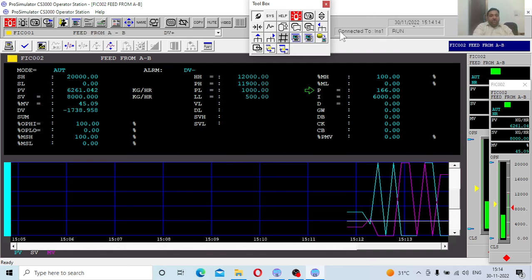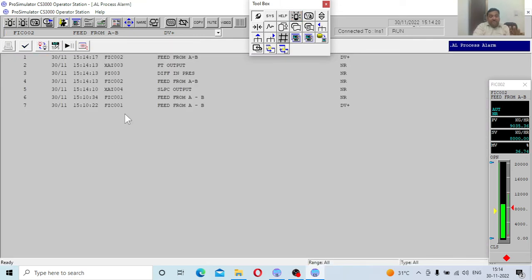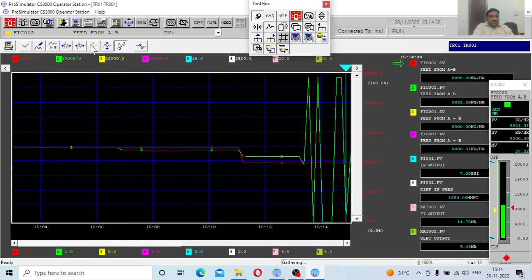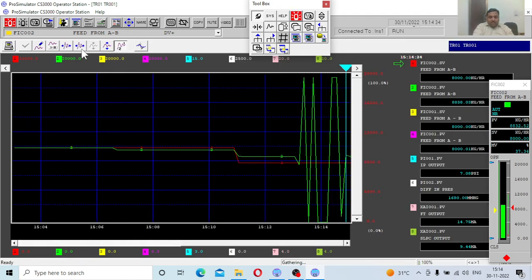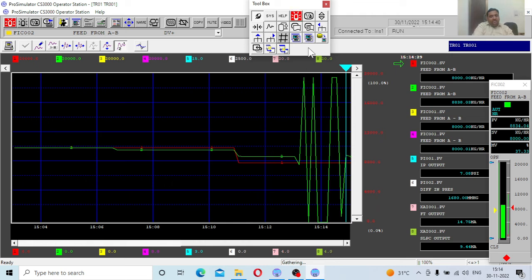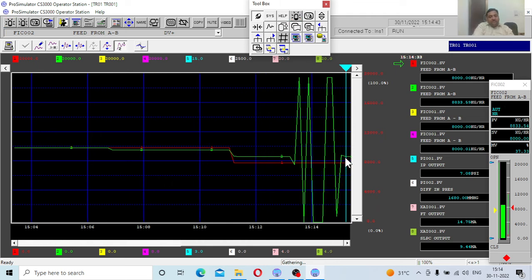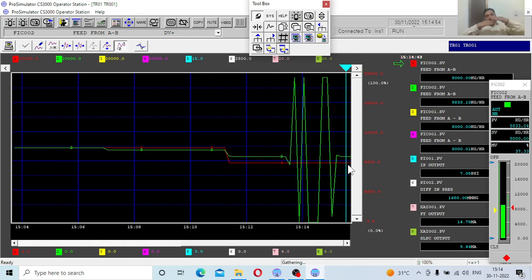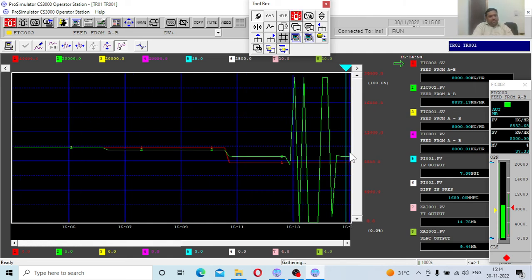Now things are trying to settle out, and the red alarms are gone — meaning no large deviations are occurring in the system anymore. If you look at the trends, earlier there were huge fluctuations with large valve opening and closing. Now you can see the fluctuations are settling, but still you can see an error between the process value and the set value — this is the basic characteristic of the P controller.